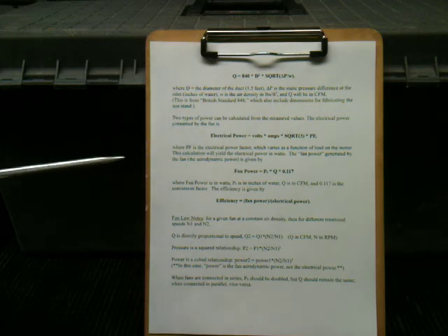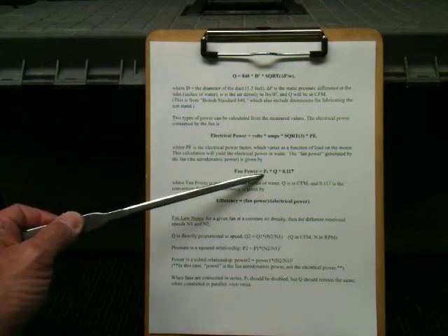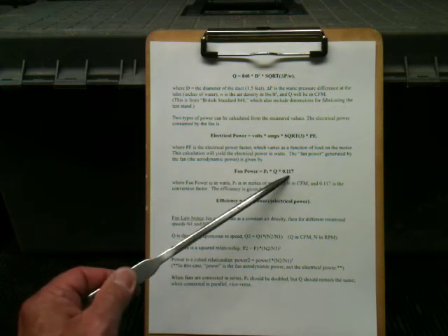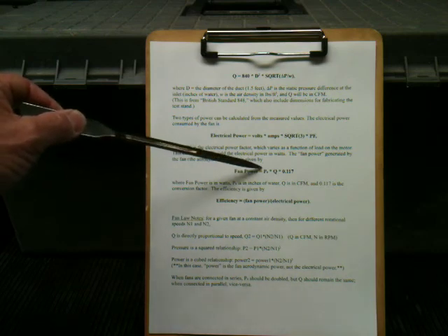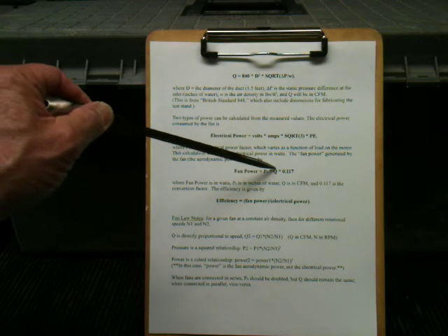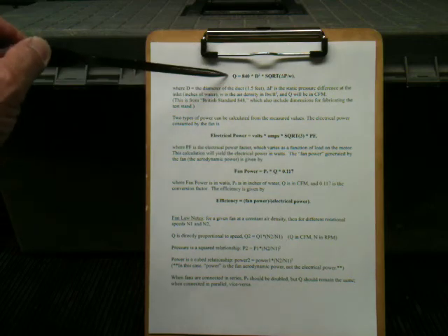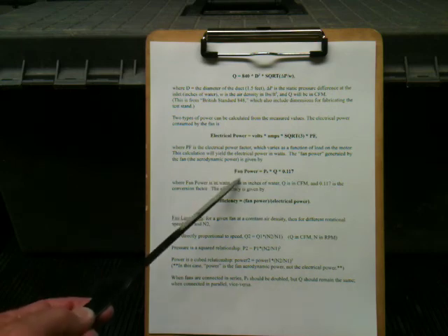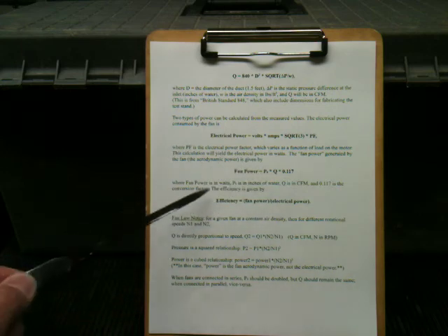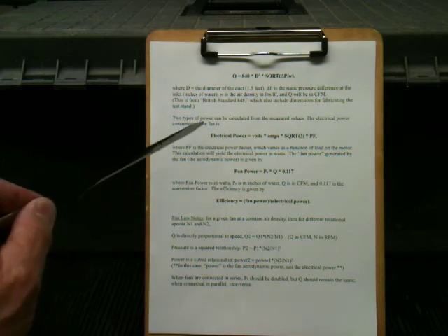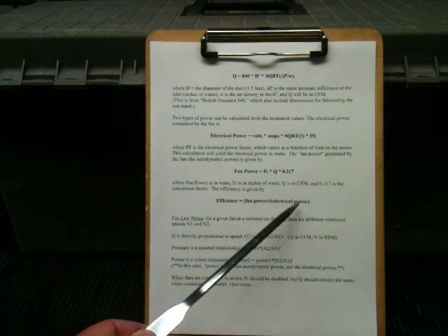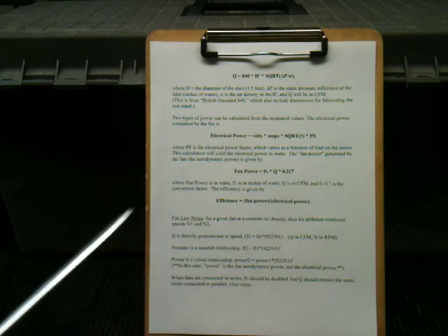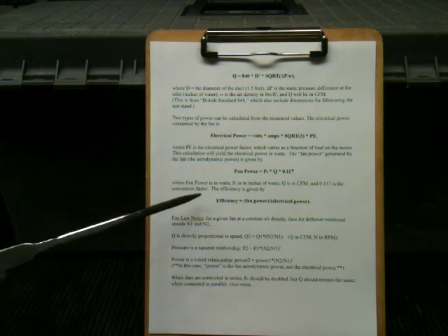Then the aerodynamic power generated by the fan itself, the fan power, is the static pressure times the flow rate times the conversion factor 0.117. So P sub S is in inches of water that you'll write down. Q is in CFM that you'll calculate up here. And then 0.117. And so you'll get a fan power, and that is going to be in watts. Okay? So this will also be in watts. So then the efficiency is simply the fan power divided by the electrical power. And that's going to be some number less than 1. Okay? Probably quite a bit less than 1 for the most part.